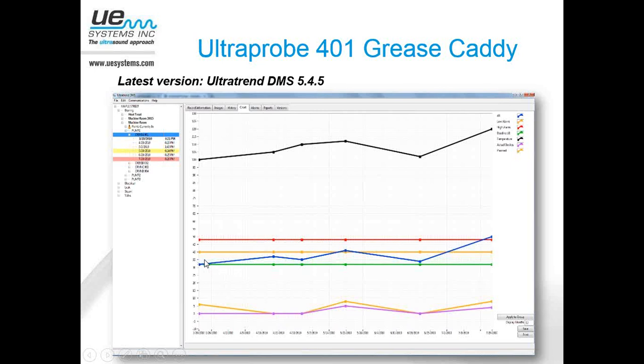This should look familiar to most of you. This is what we would typically see when we're plotting our data. So we've got 6 historical readings here. We're plotting that against a baseline and a low alarm and a high alarm. And then we've also added temperature here. If you're not sure how to do this, you would just click on whatever point over here in your hierarchy you're interested in seeing the trend of. You would click on your history tab here, because whatever is selected in the history tab is what's going to show on the chart. Your choices would be over here on the right. You would select temperature, move it over to the left. You would select actual strokes, move it over to the left, and then planned strokes, move that over to the left. And then when you click on chart, again, whatever you've selected in the history tab, that's what's going to show up on the chart.